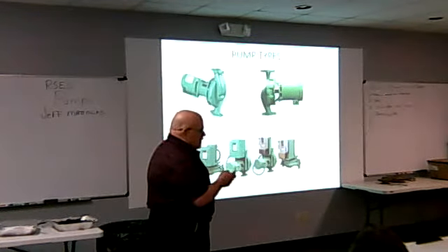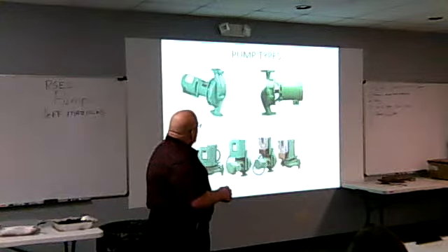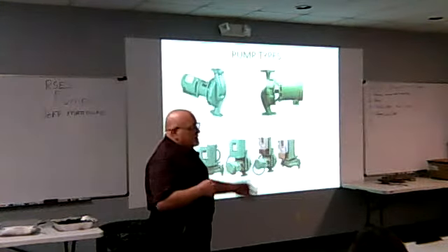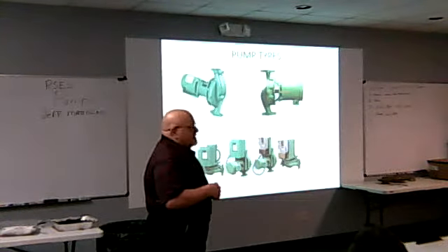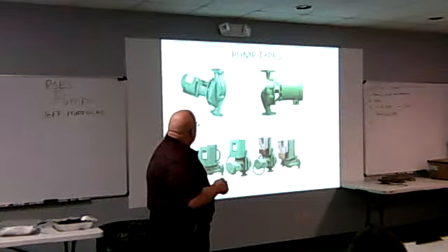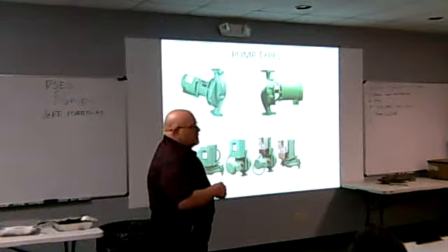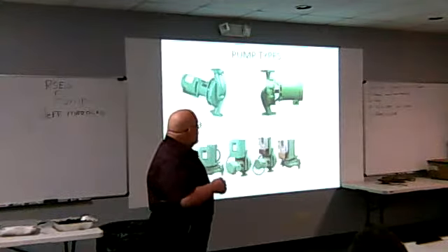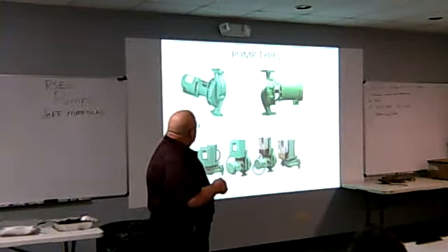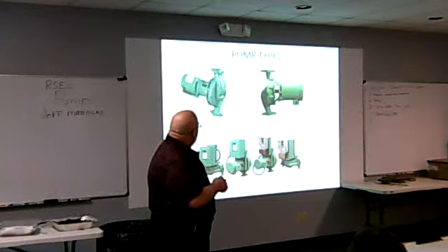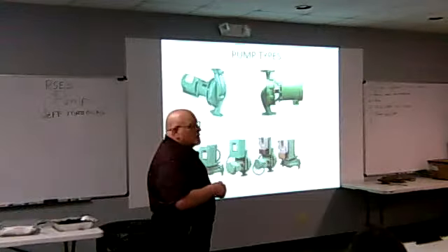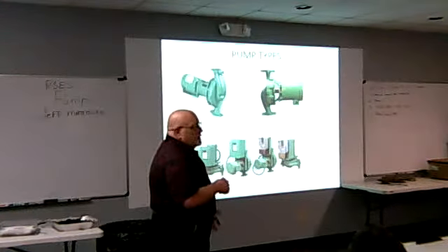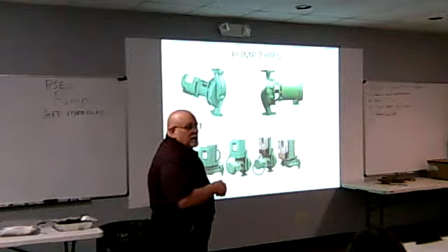Then you get a little bit bigger, commercial. These are our 1900s. The Taco equivalents would be a Series 60 and a Series 90. The 1600 actually has a coupling in here, motor. It's like a 3-piece circulator, but much larger. They go up to about 3 horse. And this is the exact same volute, except instead of having a bearing assembly in here, we're direct driven right from the impeller to the motor. So you have a seal kit, but no bearing assembly.